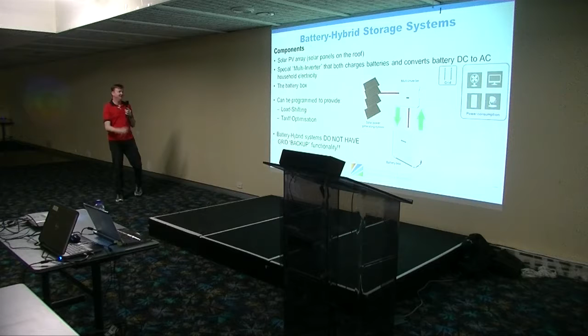It's a safety thing, because if that inverter still produced power during a blackout, that's potentially putting power back into a live faulty cable in the street, which is potentially putting linesmen at risk. They're trying to fix a faulty line, and the system's still putting power out to that line. So the inverter must shut down within 2 seconds of sensing a power outage.